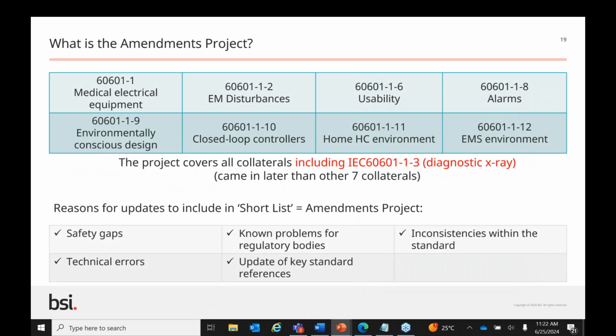So what is the amendments project? It consists of the general standard 60601-1 in the upper left-hand corner, the EM disturbances, the 1-2, usability, the 1-6, and all the other collaterals in the rectangular box, plus the diagnostic X-ray standard, the 1-3, just below the rectangle. SC62A is the technical committee in charge of the IEC 60601-1 and the collaterals in the 601 series. And yes, I abbreviate 601 or 60601-1.